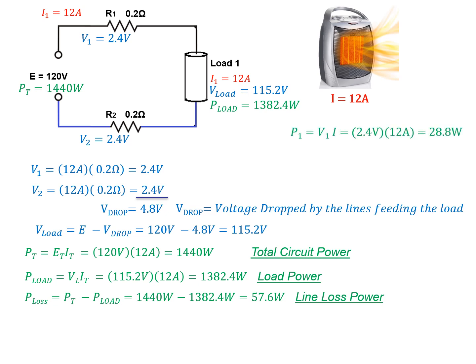We could also calculate how much heat or power is being dissipated in the wires by simply multiplying the current through the wire by the voltage drop of the wire. In this case, each wire is going to dissipate 28.8 watts for the total of 57.6 watts of line loss.